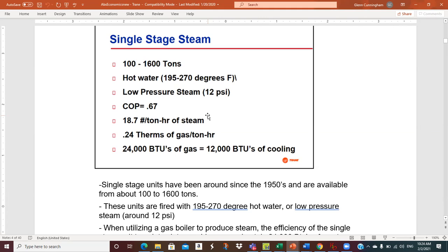When we're dealing with these energy flows, we always have to be clear. You can't say that an amount equals a rate. If you do, you're screwed up. It's like saying that a degree Fahrenheit equals a PSI. They're different birds. Okay, so a 1 ton hour of refrigeration is 12,000 BTUs, right? Because it's a rate of 12,000 BTUs for 1 hour. So it's 12,000 BTUs, an amount.